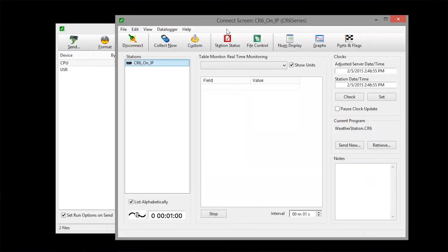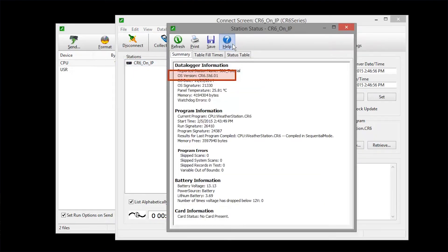Today I showed you two ways to send an OS to your data logger. Using the Device Configuration Utility, all data and programs were deleted and settings were set to factory defaults — though using the backup and restore features makes restoring settings and programs easy. For remote connections, we use File Control through the Connect screen. This takes more data logger preparation, but results in settings and programs being retained. You'll need to restart your program, and remember all data will be deleted. Please contact a Campbell Scientific application engineer to discuss your application and for answers about sending an operating system to your data logger.